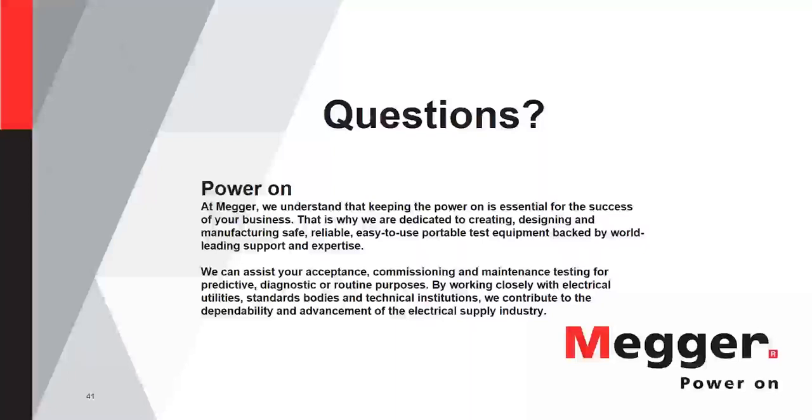So you always want to start off with a fully charged and equalized battery before you perform your testing. The only thing I'd say is, if for some reason your testing equipment did trip, you are allowed one stop within your testing for either 10% of the total test time or 6 minutes, whichever is less. Generally with the testing, we usually end up at 6 minutes. So if you did have that, you could stop it and fix the issue within 6 minutes or 10% of the total time, if you needed to.